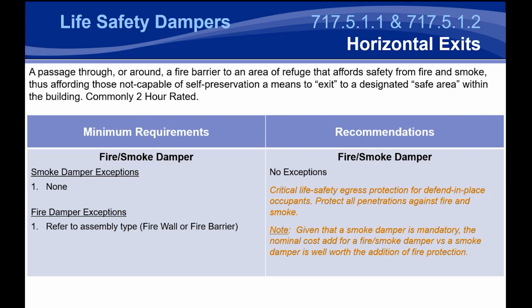Now, any duct penetration for this, which is typically uncommon, would have to have a fire smoke damper because you want to make sure there's no fire that gets in, and more critically, you want to make sure there's no smoke that gets in that gives the occupants at least 2 hours of protection. Typically, that's not needed. A lot of times, firefighters are able to help get people out, but this is a designated safe area that's a shelter in place type situation. And it's very rare that there are duct penetrations for these types of applications.